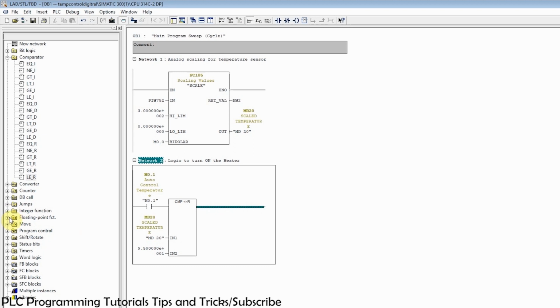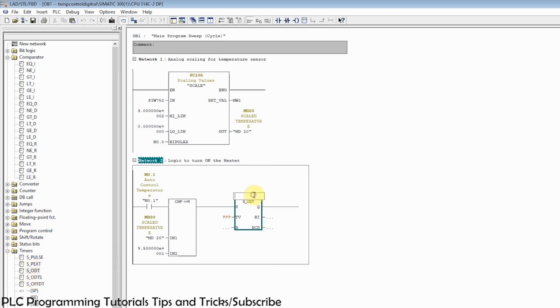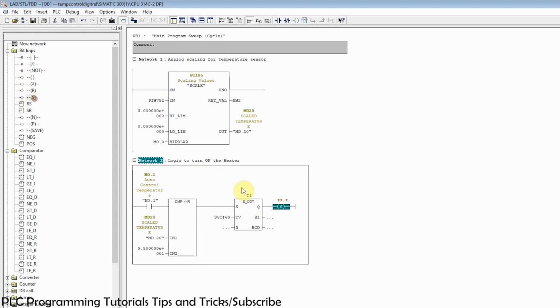Next, we will insert the on delay timer with 6-second delay. So whenever the temperature is less than 95 degrees Celsius for 6 seconds, it will turn on the heater coil Q0.0.